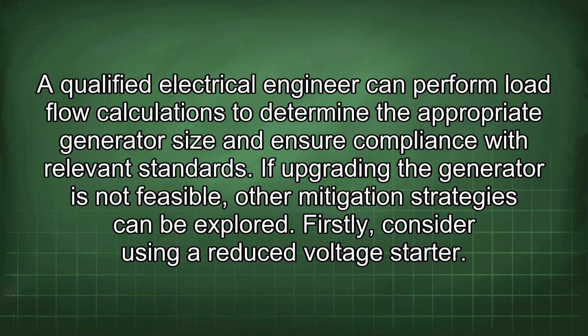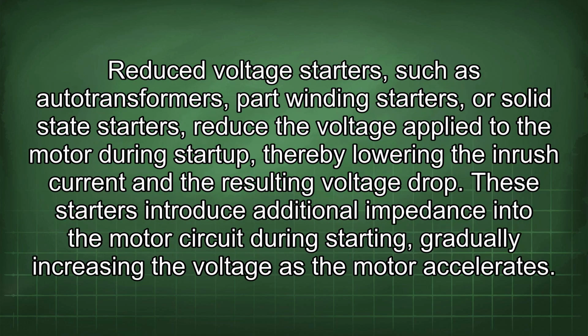Firstly, consider using a reduced voltage starter. Reduced voltage starters, such as autotransformers, part winding starters, or solid-state starters, reduce the voltage applied to the motor during startup, thereby lowering the inrush current and the resulting voltage drop. These starters introduce additional impedance into the motor circuit during starting, gradually increasing the voltage as the motor accelerates.